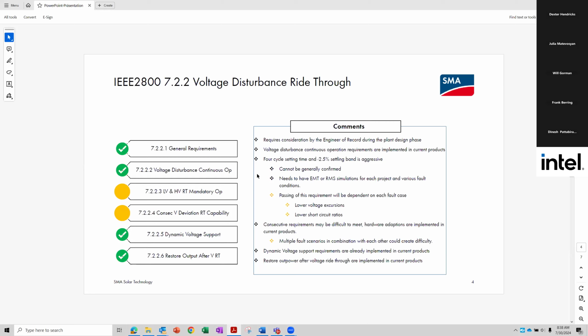Consecutive voltage, as Dinesh mentioned, is not something that the inverter really gets affected by. However, the type of fault that can happen consecutively does play a part. Again, the excursion of the voltage from nominal, as well as the short circuit ratio availability at the POC, will all play a part. These need to be confirmed on a project-wise basis through modeling, PSCAD, EMT type modeling. Dynamic voltage support, again, we generally can meet, shouldn't be a problem. And restore output after a voltage ride-through event, we can generally meet.